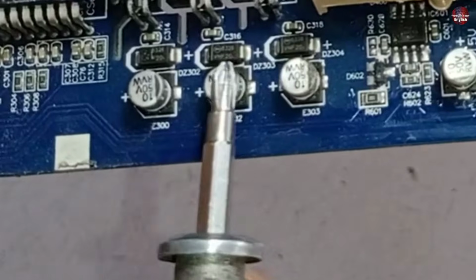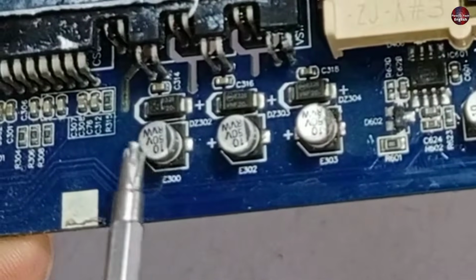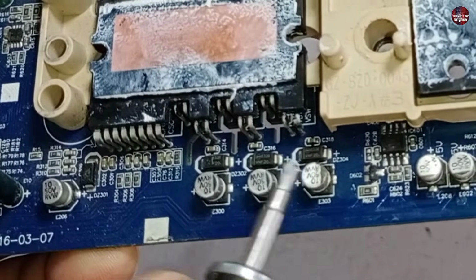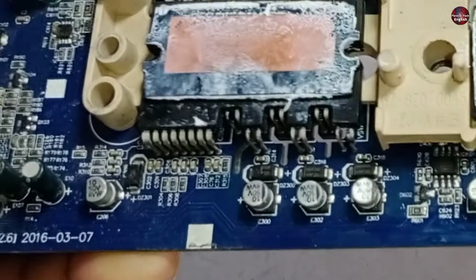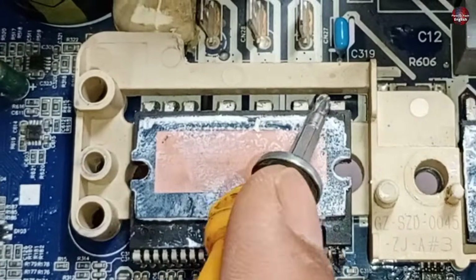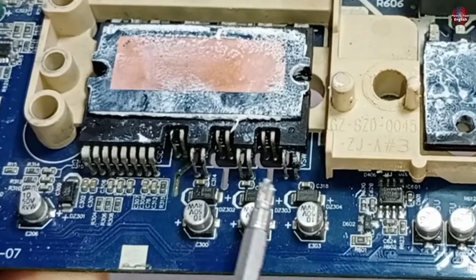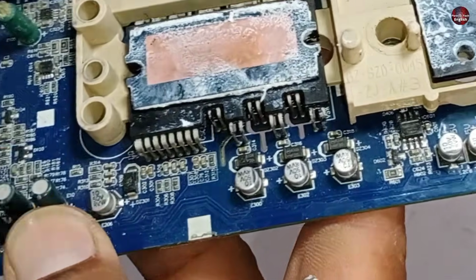These three capacitors are biasing capacitors, meaning that the controlling voltages pass through them. The IC installed in the IPM is controlled by these capacitors. The IPM will not work if no voltages are present here. The IPM will seem fine on the high side pins, but will show the P4 error code. Now the need is to work on the low side pins of the IPM.